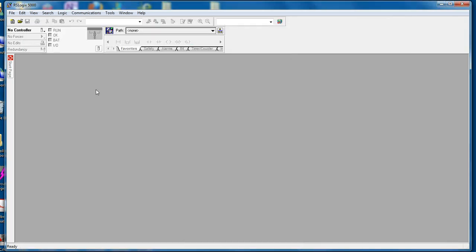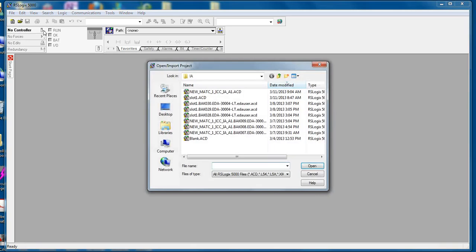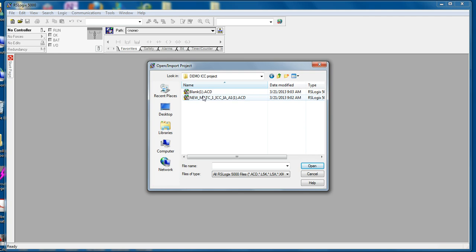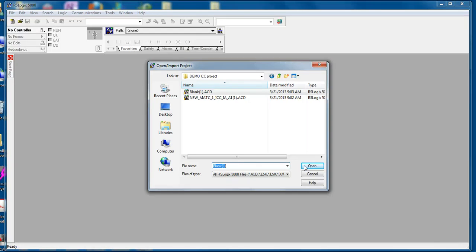I already have RSLogix 5000 software running. Click open, navigate to the folder that you download the files to. You note there are two files here. We want to do the blank one first. Since our 10-rack ControlLogix chassis contains two processors, we want to be able to load the blank ACD file into the secondary or redundant processor.